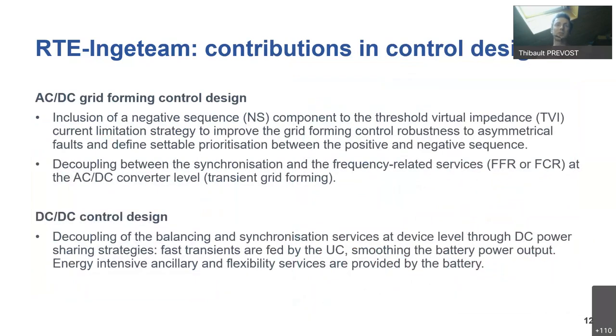If we go to what has been done there, I believe one of the main differences with the MIGRATE control is that we have a negative sequence control added on top of the threshold virtual impedance, which means we can deal with unbalanced conditions and unbalanced faults. You can also, in fact, set how much positive and negative sequence you want, if you want more positive voltage, I mean, a balanced voltage or balanced current.